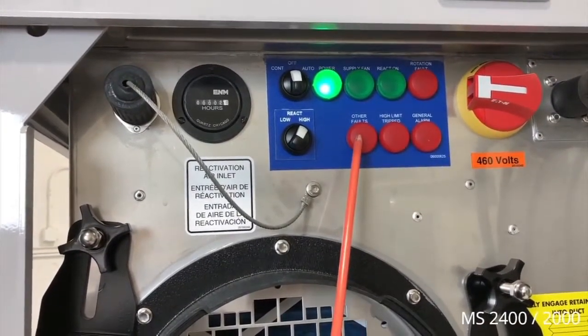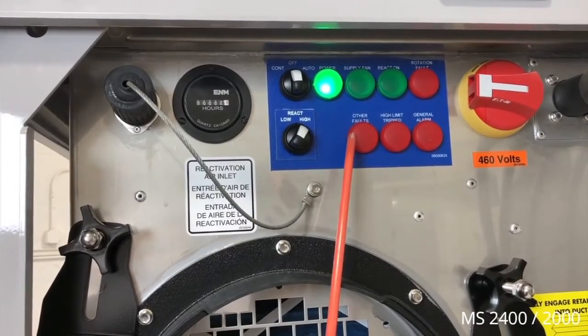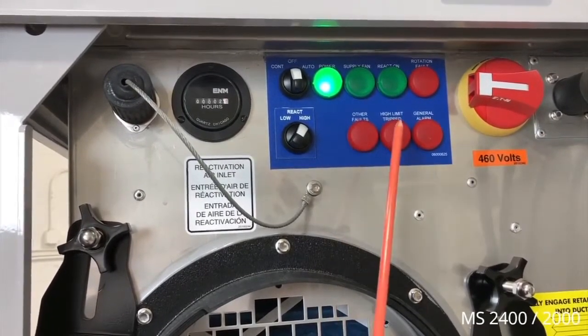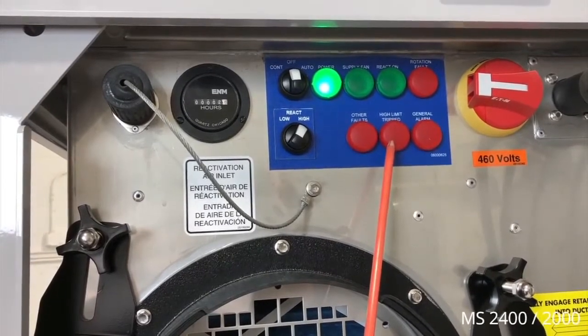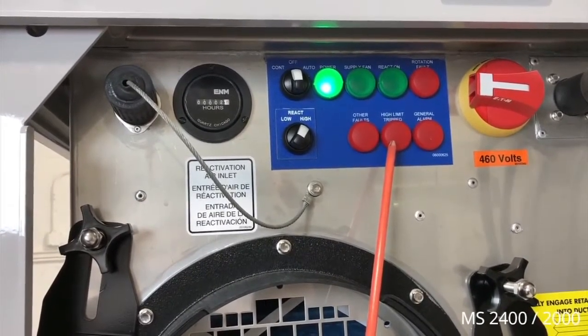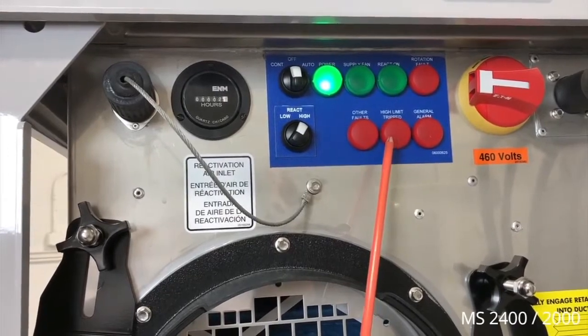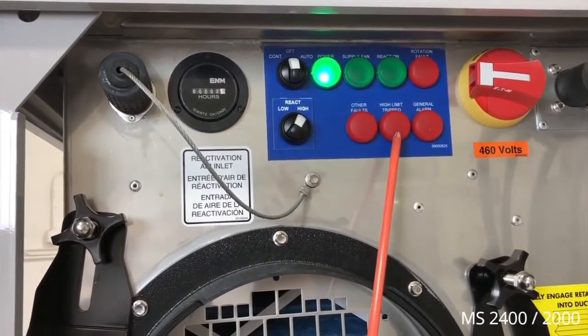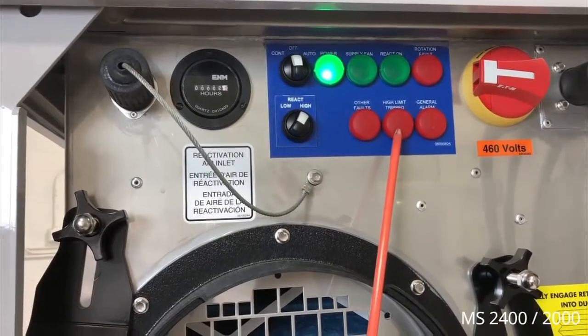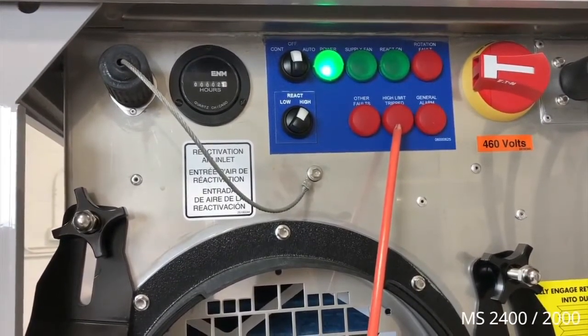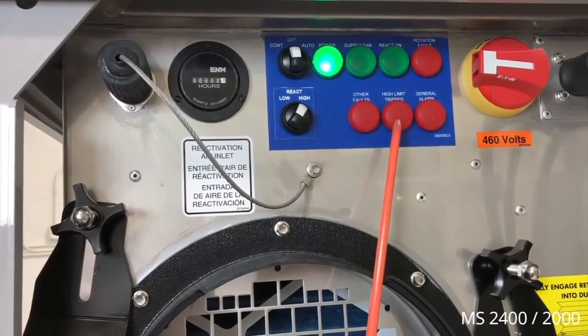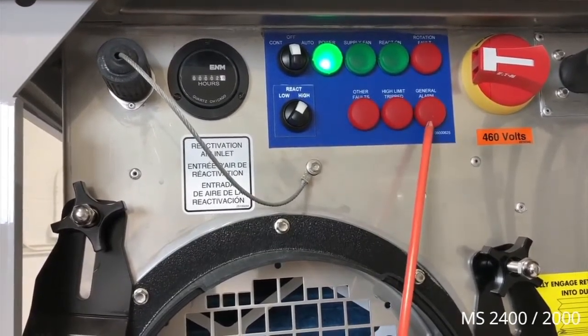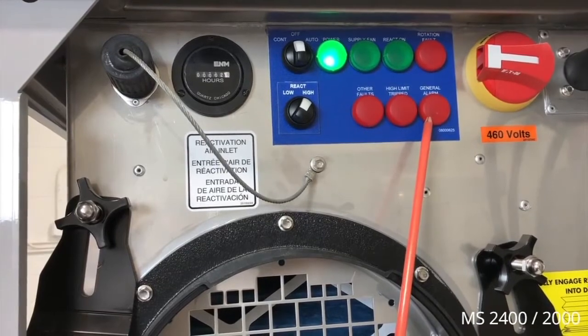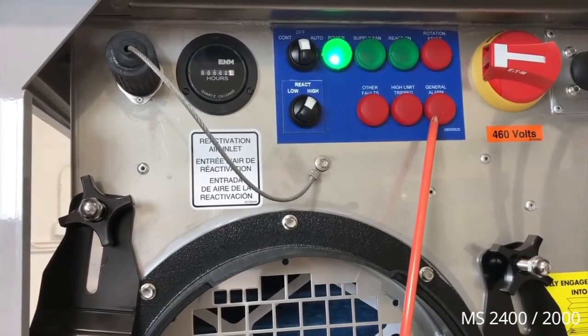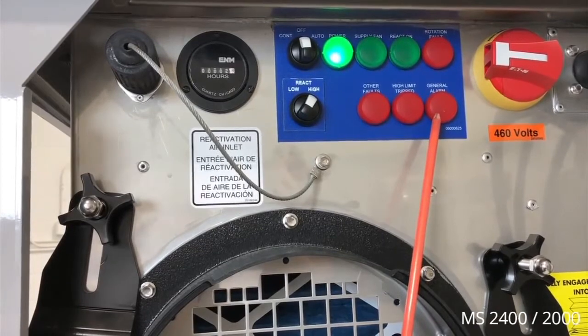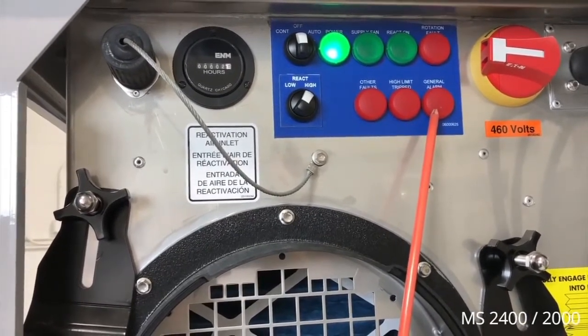The first light, the other faults, indicated a phase issue with the electric power input. The second is a high limit, which measures the reactivation heater temperature and will shut it down in case of a problem. This can be caused by a reactivation filter being dirty or a reactivation duct being closed or drawn shut. The third is a general alarm. And if this alarm lights, we go back to the microprocessor, and the microprocessor has a fault screen that will indicate what might have caused the general alarm.